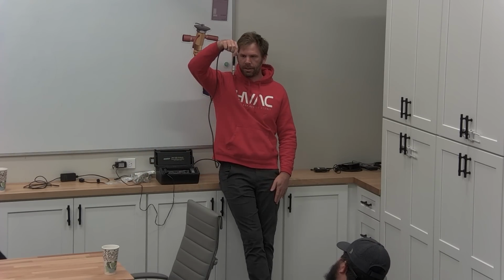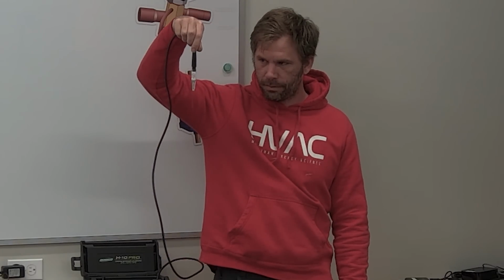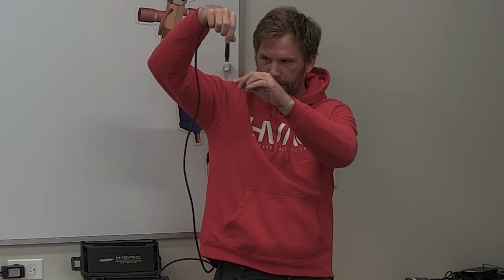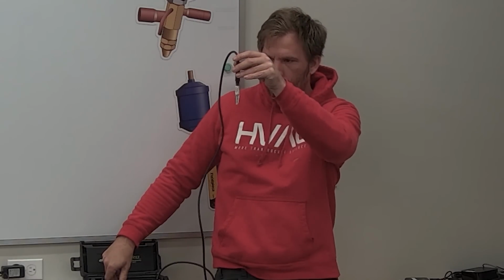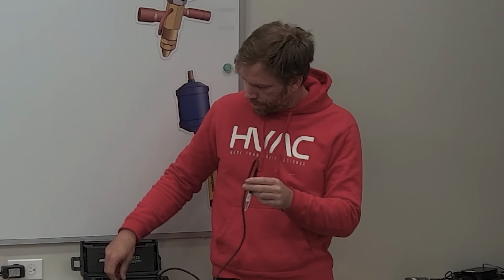could have failed. And so to test that, you have your little airflow indicator in here. If you're looking at it really close, you could see a little bit of movement on this. Like right now, I have a little bit of movement. If I switch it to large, I have a little bit more movement. Large leak just pulls in a lot more air. And so, anyways, to test it, we're going to cover our hole and remove the hand, and you should see the ball bounce up in reaction.